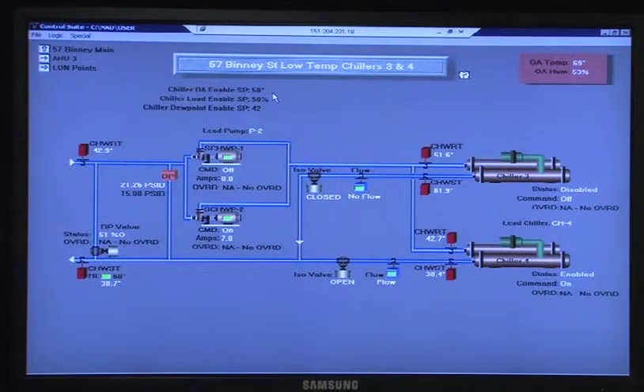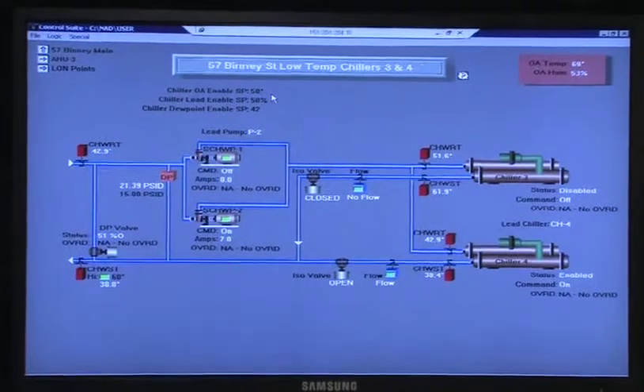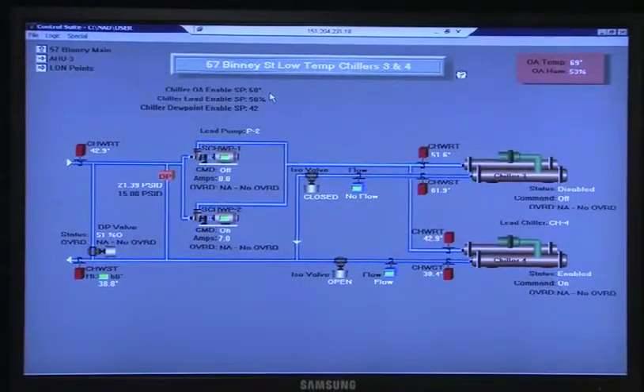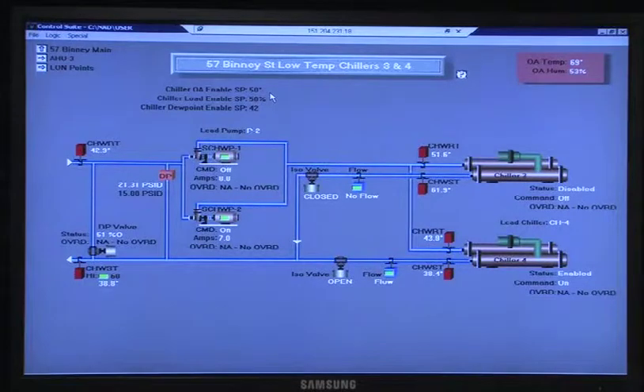So the only other thing that's unique to this is we're modulating the... Well, Frank, we don't have chiller load. That was left on there. The original intent, we didn't scrap it yet. So that's coming out, and we'll just put the lag call with the dew point set point, so you guys can see it. And then I'll have Jamie put the dew point on the screen too, just to let you understand what I mean by enthalpy.